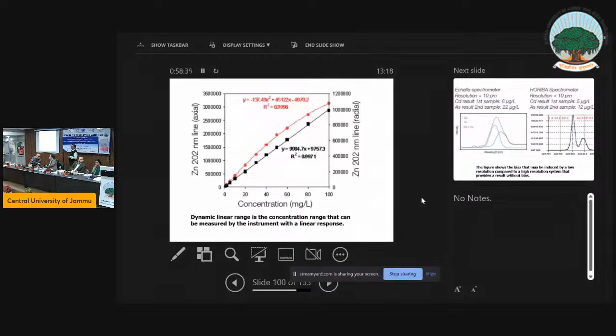spectrometer resolution. There are 3 peaks here, and there are 2 peaks here, because the resolution is less than 10 picometer, and this is 10 picometer. So it cannot resolve. It cannot mark and show you 1 peak. As on date, the resolution we have achieved, I think 7 picometer we have gone down. 5 picometer is also available. So if the lambda values differ by 7 picometers or 5 picometers, you will have 2 peaks.